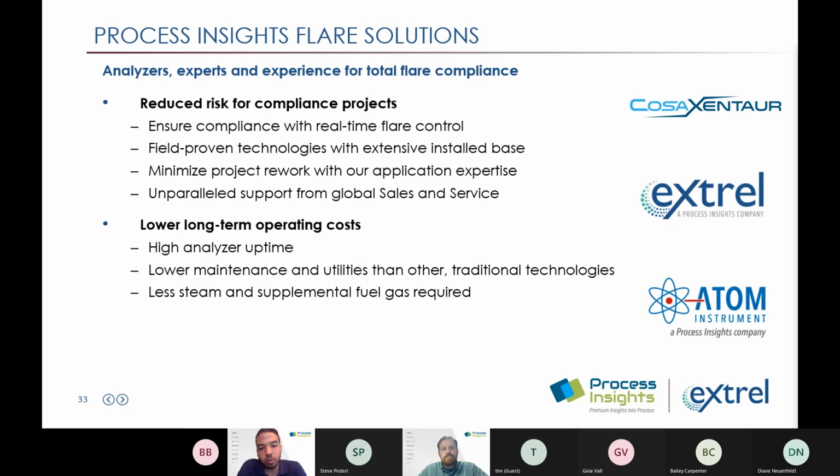All the main maintenance items, we usually take about 2 days to go through the entire procedure and teach about troubleshooting and calibrating. So a lot of our customers have elected to maintain the instruments themselves. The analyzer is designed with serviceability in mind. We checked earlier in the year, and we've got about a 50-50 split with our industrial customers in the U.S. between those that elect to do the service themselves and those that opt for a contract at one level or another.